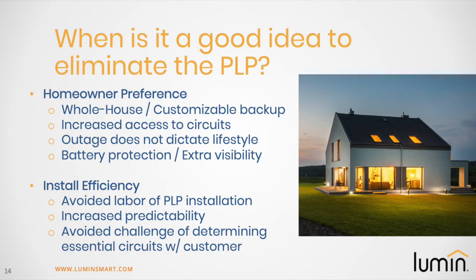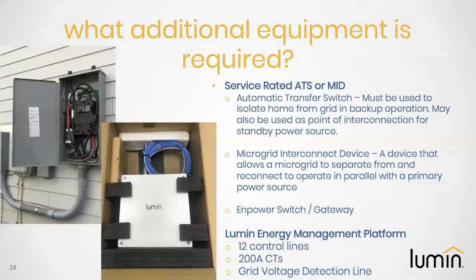So next I'll go over what equipment is required. Once it's been established that whole house backup, or eliminating that protected loads panel, is the way to go, there are really two key pieces of equipment that must now make it into the system design. The first being a service rated ATS, automatic transfer switch, or microgrid interconnection device. In order to isolate from the grid during an outage, a service rated ATS or MID must be included. An automatic transfer switch may be used to isolate the home from the grid in backup operation, and it may also be used as a point of interconnection for your standby power source, such as that generator or that battery system.